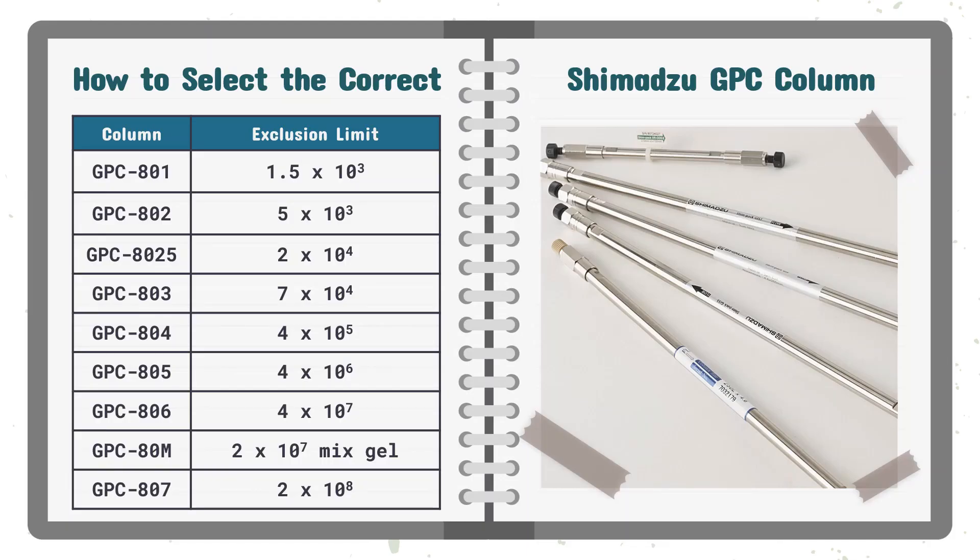There are two essential hardware components of GPC that will be introduced in this video. The first is the column. GPC columns are typically packed with porous particles made up of polystyrene polymers of various diameters and pore sizes. These are determined by the different degrees of polymer cross-linking. The variety of columns available have exclusion limits ranging from 1,500 to 200 million, providing more options to select a column optimized for separation at the target's molecular weight.